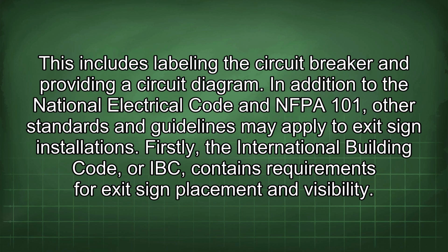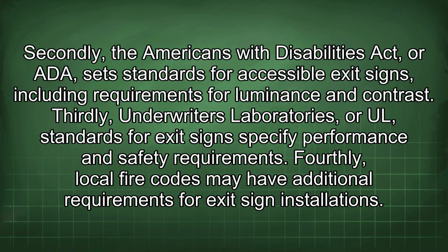In addition to the National Electrical Code and NFPA 101, other standards and guidelines may apply to exit sign installations. Firstly, the International Building Code, or IBC, contains requirements for exit sign placement and visibility. Secondly, the Americans with Disabilities Act, or ADA, sets standards for accessible exit signs, including requirements for luminance and contrast. Thirdly, Underwriters Laboratories, or UL, standards for exit signs specify performance and safety requirements. Fourthly, local fire codes may have additional requirements for exit sign installations.